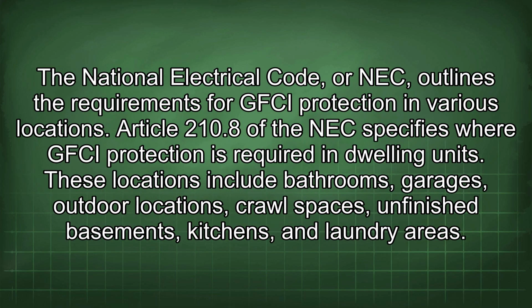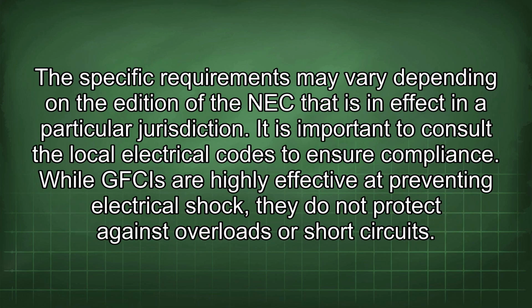The National Electrical Code, or NEC, outlines the requirements for GFCI protection in various locations. Article 210.8 of the NEC specifies where GFCI protection is required in dwelling units. These locations include bathrooms, garages, outdoor locations, crawl spaces, unfinished basements, kitchens, and laundry areas. The specific requirements may vary depending on the edition of the NEC that is in effect in a particular jurisdiction. It is important to consult the local electrical codes to ensure compliance.